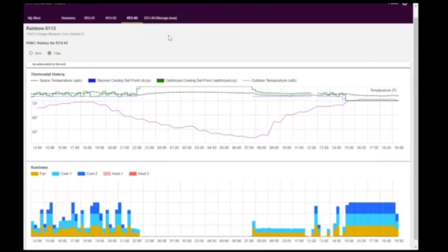In order to do that, it waits for an occupied period because of the building schedules. We know when people are not there. We also use a few other pieces of context and information, like if someone changes a set point or an occupancy sensor changes, we disable our step testing. What it tries to do is turn every RTU off for 30 minutes, turn only one of them on for 30 minutes, and then turn everything off for 30 minutes and repeat this process until it has a model where it can eliminate disturbances and only observe how one unit affects the entire building.